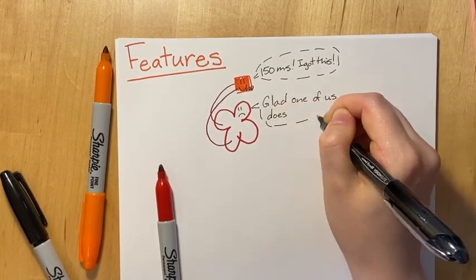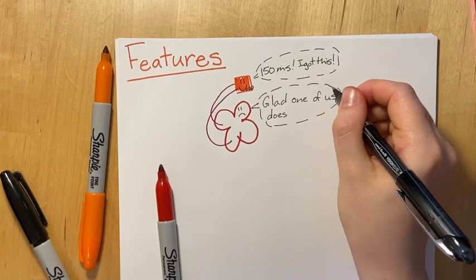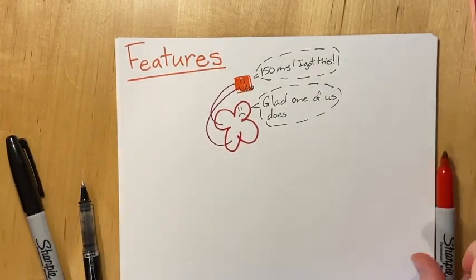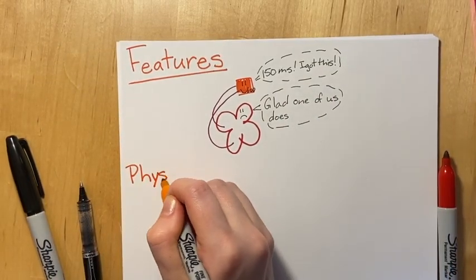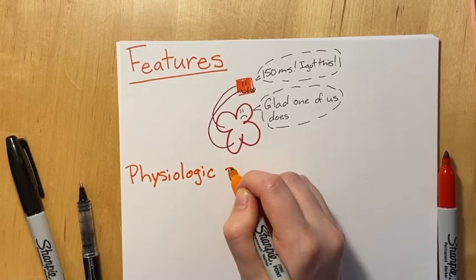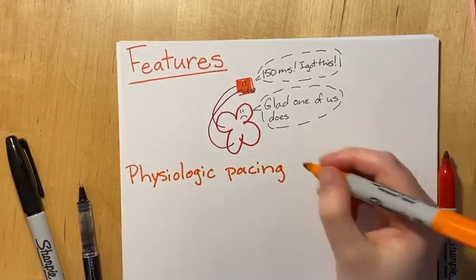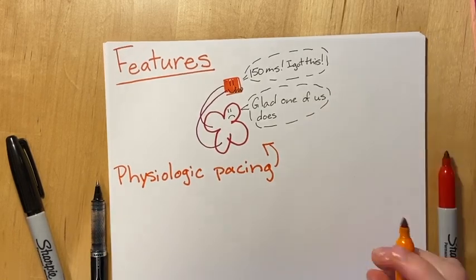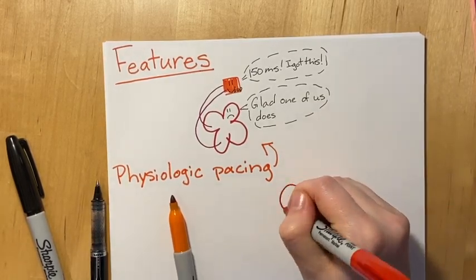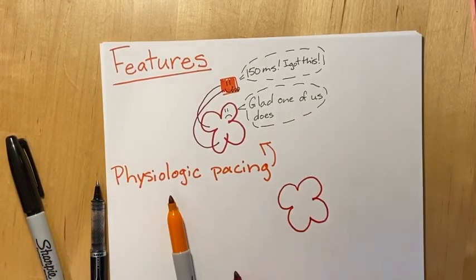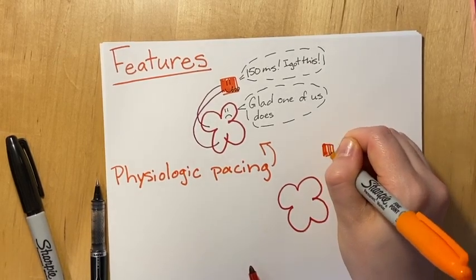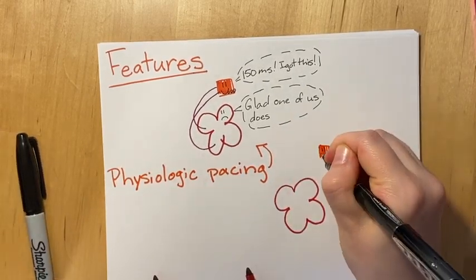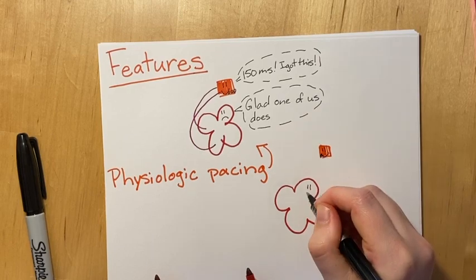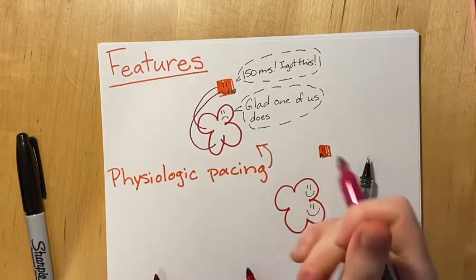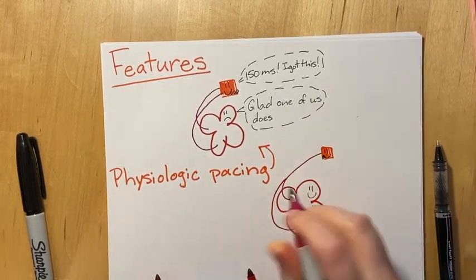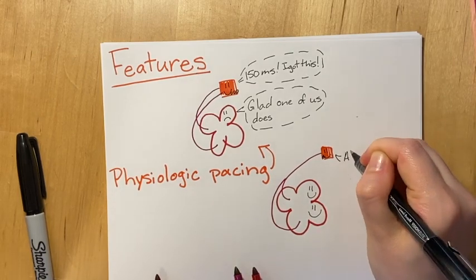Physiological pacing focuses on the AV timing interval. This allows for as close as possible a delay to mimic a normal rhythm and still give enough time for filling. This sweet spot is around 150 milliseconds in a normal person. This rate can also be set based on heart rate to compensate for normal shortening of the AV interval during exercise.